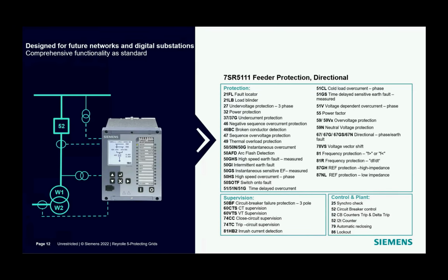32 power protection can also be used as overpower or underpower protection, depending on the setting you choose inside the software. And each stage can be set to non-directional, forward or reverse directional. So it's quite a flexible thing to choose. In addition to those protection functions, there are also the impedance-based functions: 21FL fault locator and 21LB load blinder. And as a last remark, I would like to emphasize that 79 auto reclosure and 25 synchrocheck functions are always included as standard. Depending on the I/O quantity and composition, 7SR5 protection relays are available in all three sizes: size 6, size 8, or size 12, of course, coming from smaller to larger.